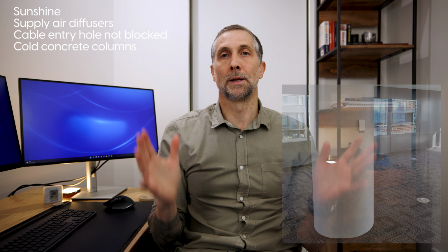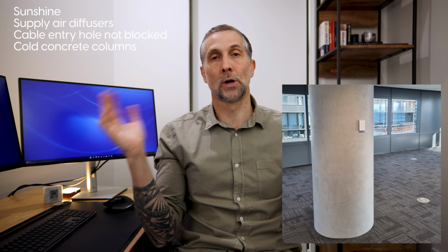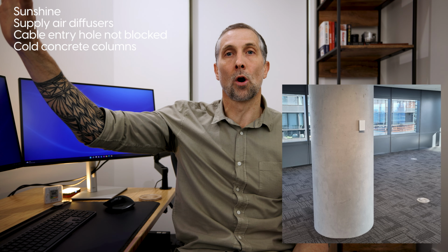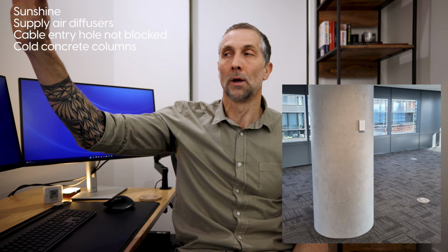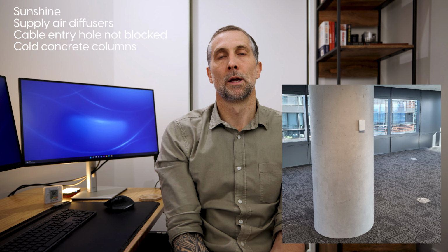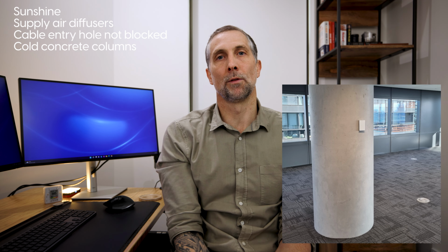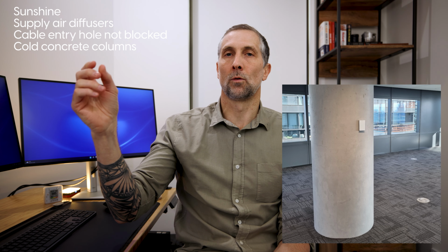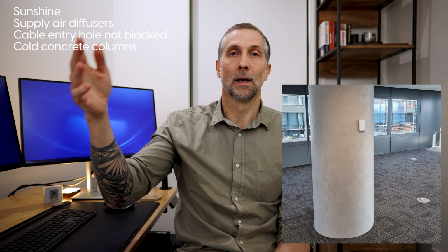Sensors on cold concrete columns, get them all the time. I'm doing an inspection, I'll walk through a new construction site, put my hand on the concrete column, and it's quite cold. And the temperature sensor, the little element, can just pick up that little bit of coolness radiating off the concrete column. So your sensor reads a 0.5 degree or 1 degree less than the rest of the temperature in the zone. The temperature sensor is not accurately representing the temperature in the zone.